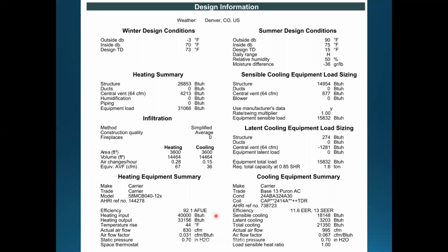So it's either 10 or 20% derate. So how would you do that? Well, you take 40,000 times 0.921 because that's just how efficient it is. Then you take that answer times the altitude derate. In this particular case, it was another 10%. So we took that number times 0.9, and that's how you get this 33,000. So it's key that this is done for altitude and gas fired. Now it's going to be different when we talk about air conditioning stuff, and we'll get to it.